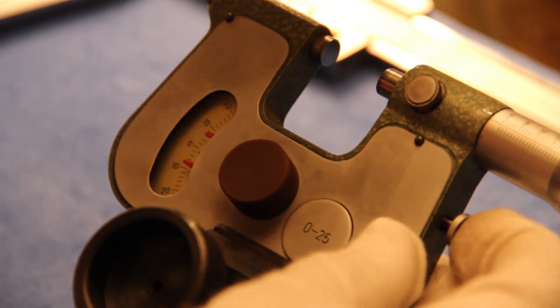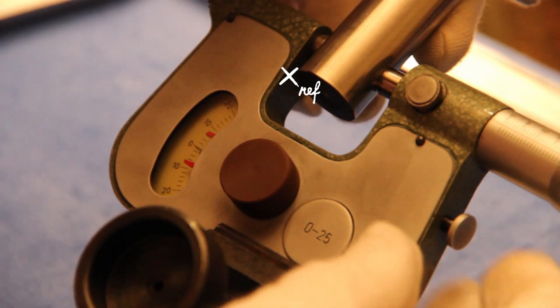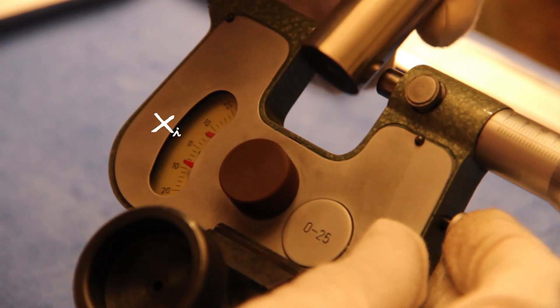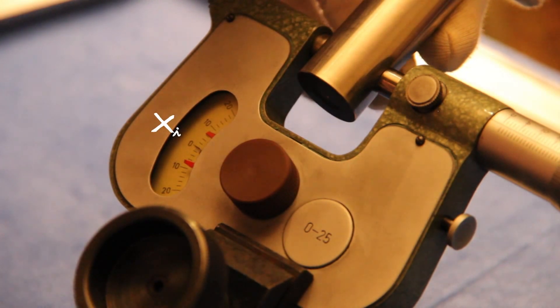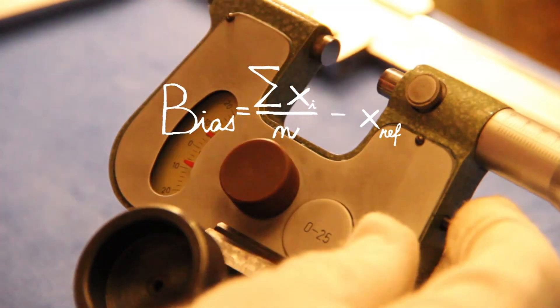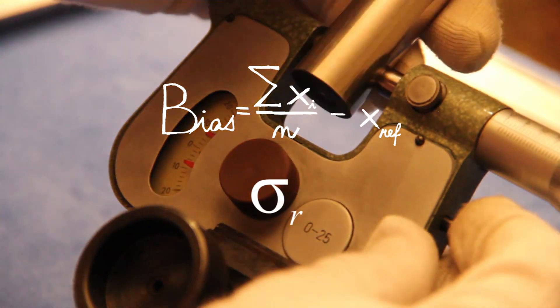Choose one part or a master of a known dimension that will be used as a reference value and have an appraiser to measure the part repeatedly, at least 10 times. Calculate the average bias and the standard deviation of the repeated measurements.